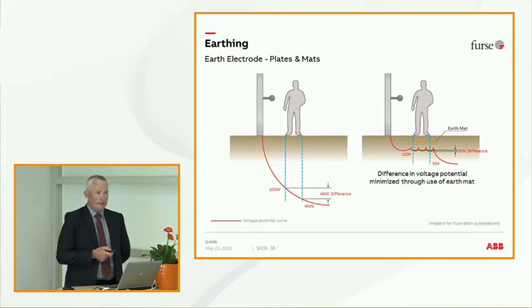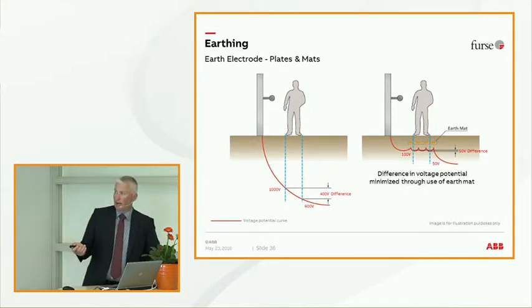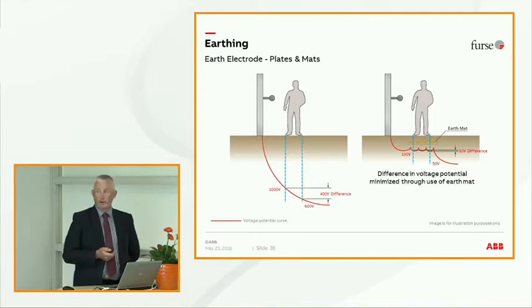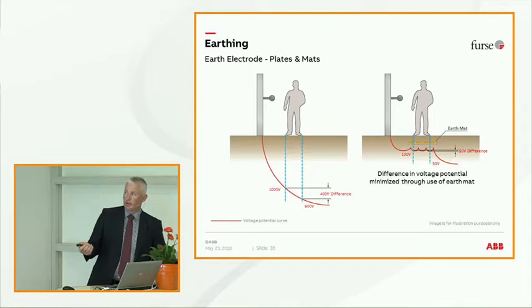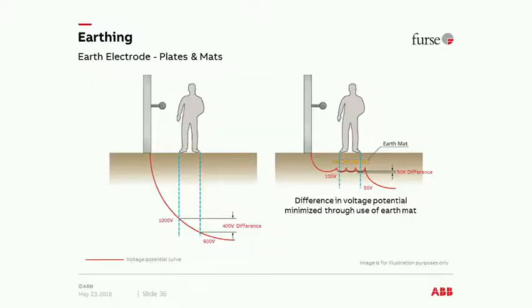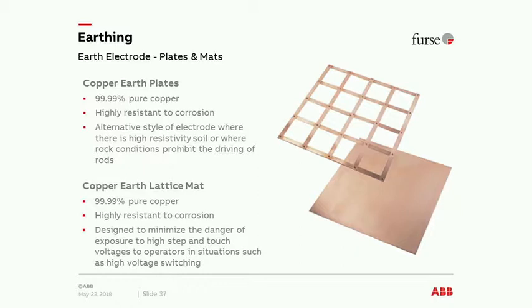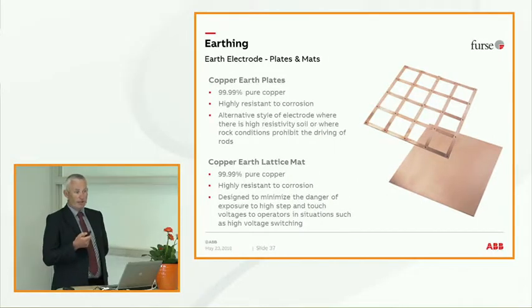When we're looking at earthing, I'll explain a little bit later, but this is the area that causes the problem. It's when you've got a difference. So if you've got an operator and a machinery, and that becomes live due to a fault, it's this difference that causes the issues. There are often solutions: a grid of copper, or in this instance, we've used a copper mat. You'll see these in different sorts of materials. So when you're doing your earthing system, it's all about safety and saving lives.